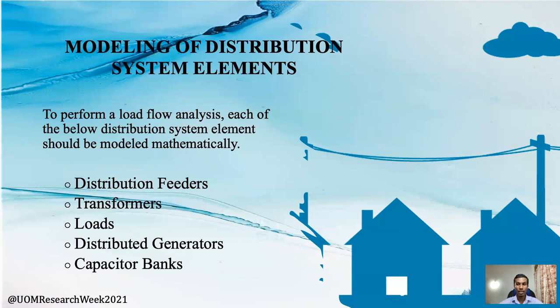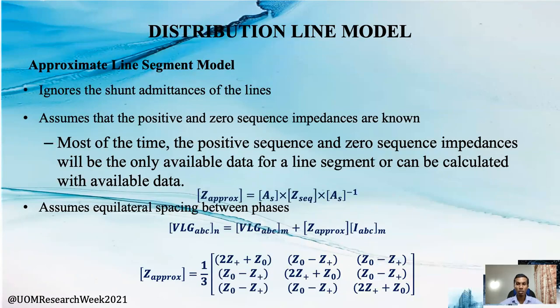Before carrying out load flow analysis, the distribution system model components should be modeled mathematically. For distribution lines, we selected the approximate line model. It performs calculations using data such as conductor diameter, length, and line spacing, ignoring shunt admittances. In practical scenarios, most of the time the available data are positive and zero sequence impedances. Considering this and the simplicity to implement in the algorithm, we selected this model.